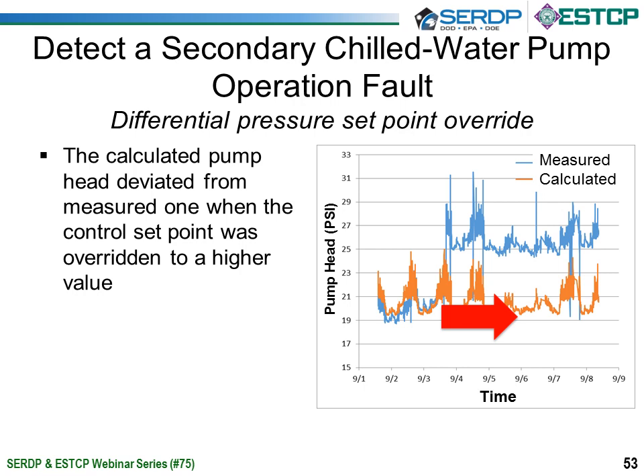The second example of a fault being detected that I want to point out is a case where we implement a change in the differential pressure set point for this chilled water pump. So we're mimicking, in a sense, an override of this set point that was either intended to be put in place temporarily and then put back to its usual value, and that was neglected and it was maintained in place, or someone reset that set point to an incorrect value.